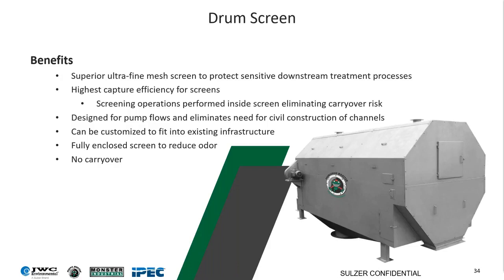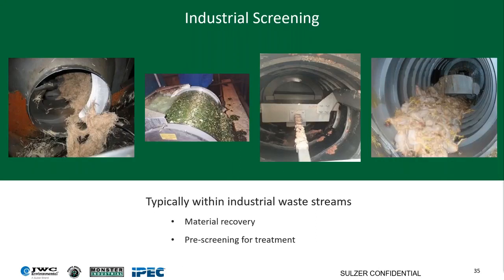Now, all mechanical equipment, including screens, can fail, and various designs fail in different ways. When a band screen fails, it's usually a sealing issue. So some trash will start bypassing the screen through a damaged seal, and that's going to directly foul the membrane. But when a drum screen fails, it's not a sealing issue. It's because the screen has become overwhelmed, and it tends to spill out onto the deck unless there's a bypass. So you get an overflow, and that's not good either, right? Nobody wants to see the inflow out on the ground. So typically we make sure that they're well protected in case of an overflow. However, in that case, there's no chance for the membranes to be fouled. So which do we prefer? Do we prefer the membranes to possibly be fouled, or do we prefer to possibly have liquid on the ground? So it's six in one hand, half a dozen in the other.